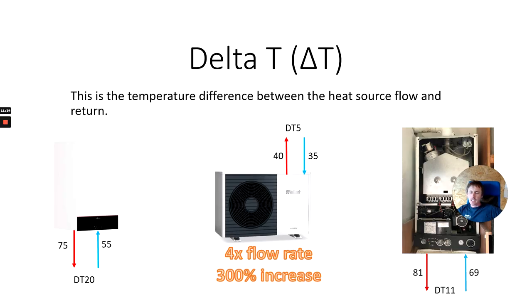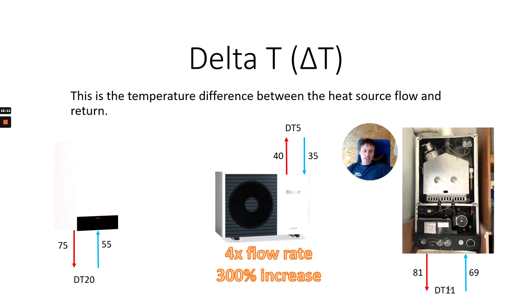Delta T is the difference between the flow and return on the heat source. For a new gas condensing boiler going out at 75°C and returning at 55°C, that's a 20-degree difference — DT20. For an air source heat pump working at DT5, going out at 40°C and returning at 35°C, we've got four times the flow rate — a 300% increase — which is why pipe sizing must change in most situations when fitting an ASHP onto a system that previously had a gas condensing combi. An old standard efficiency boiler pre-2005 going out at 81°C and returning at 69°C was working on a DT11.